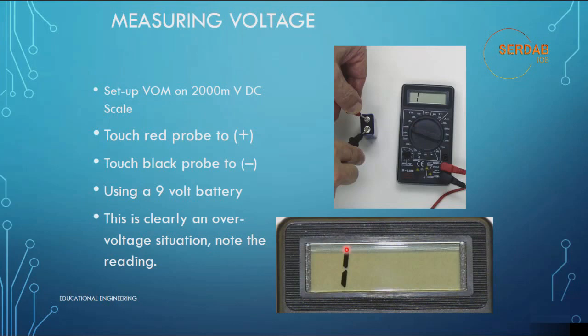As long as you do not exceed the maximum voltage value of the meter, in this case 600 volts, there will be no physical damage to the meter. The meter indicates an over voltage situation by displaying a single digit 1 at the far left. This overage indication is consistent with the other functions to be looked at later. So a 1 means that we have over voltage and we didn't choose the right resolution.